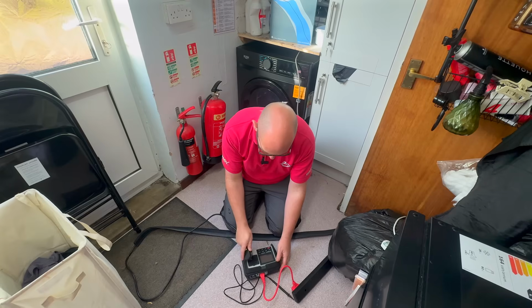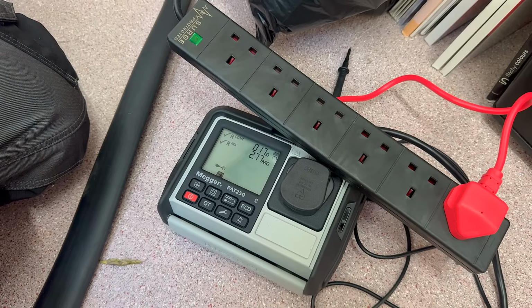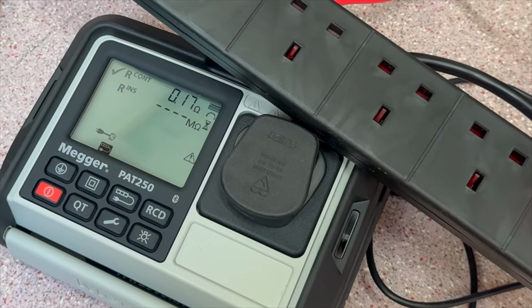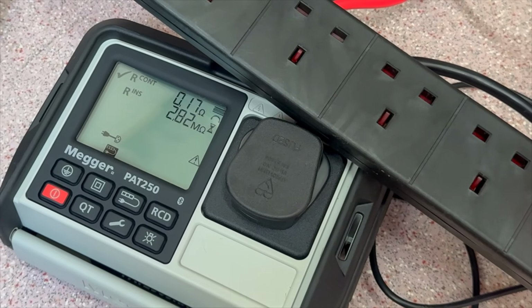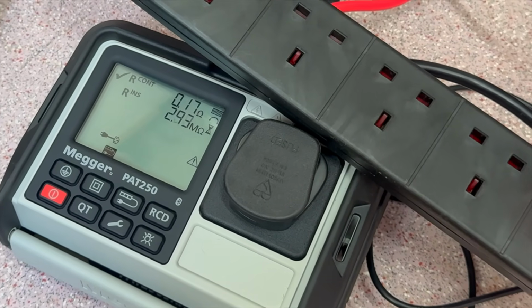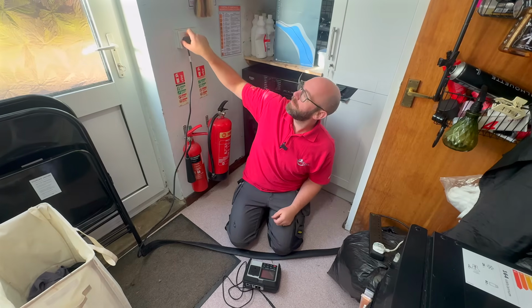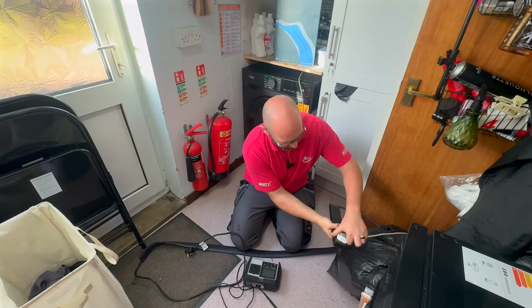Once a thorough visual inspection has taken place, the testing of an extension lead is simple enough. Plug the lead into the tester and the breakout lead from the tester to the extension socket. This creates a closed loop. We select extension lead and press go. The tester cycles through all the tests to make sure everything is okay. We do need to ensure that the extension lead meets the maximum permitted continuity of the device. But how do we know what this is, and is there a number? Well, yes there is, so let's drop out of this test and calculate our continuity limits.